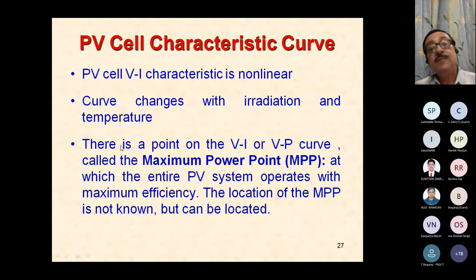Now, coming back to photovoltaic cell characteristic curves, I think most people know that it's a nonlinear characteristic for voltage versus current, and the curve changes with irradiation of sunlight and with temperature, and that there is a point on the voltage-current or the voltage-power curve, which is called the maximum power point, at which the entire PV system operates with the maximum efficiency under the given solar insolation at that time. The location of the MPP is not known, but it can be located.